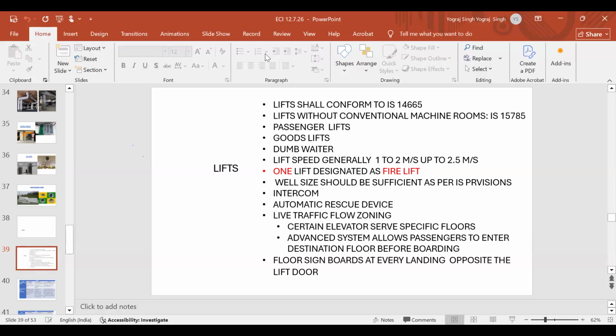Now, in your building, one lift must be designated as a fire lift because the fire lift will not be used by anybody else. If there is a fire in the building, all lifts will be switched off. That is why we tell the occupants, please rush through the staircase. In case of lift, it is made dead. And there is only one lift which is functional. It is directly connected to the DG set supply. The fireman will first see whether it is safe to use this lift or not. Then they will use this.